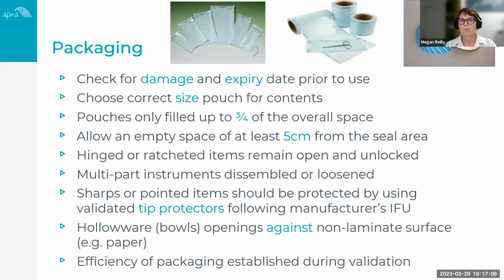Make sure that you choose the correct size. So whether it's a laminated roll or a pouch, you want to be able to contain all the contents. Only fill the pouches to 3/4 of the overall space. Make sure you leave adequate space at the end so that you can actually open the packaging in an aseptic manner. Remember that any hinged or ratcheted items need to remain open and unlocked. Any multi-part instruments need to be disassembled or certainly loosened. If you have sharp pointed items, they should be protected by using validated tip protectors, following the manufacturer's instructions. With any bowls or hollowware that you use, the openings are always against the non-laminate surface, for example the paper, so that we can allow for the water vapour to be removed during the sterilisation process.